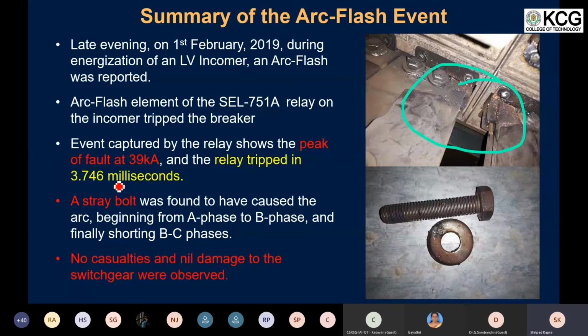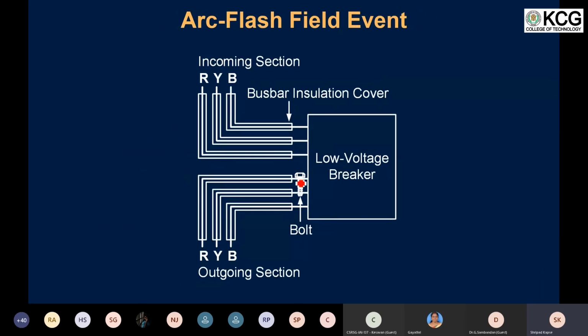When we further investigated the possible cause of the arc flash, it was due to a stray bolt that was left on the outgoing leg of the LT breaker. So let us try to understand where exactly it was. There was a stray bolt left on one of the outgoing legs of the LT breaker. This is again a 415 volt breaker, and the incoming side is connected to the 415 V/11 kV transformer, and the outgoing side is connected to the feeders, which in this case are the battery storage inverters.